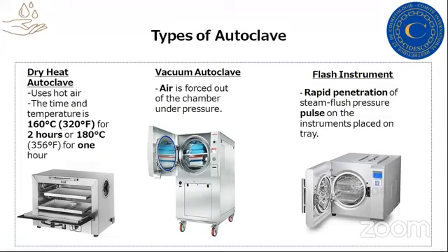Now let's see in another slide what types of autoclaves are available in the market and who uses them. You can see three different kinds of autoclave: dry heat autoclave, vacuum autoclave, and flash instrument. All these three are generally found in clinics and hospitals, wherever there is cutting, stitching, and a lot of blood coming on the instruments. So dry heat autoclave is again the hot air. The temperature this time is 160 degrees Celsius, which is 320 degrees Fahrenheit.